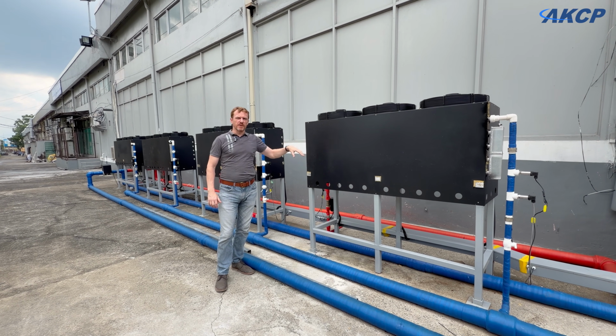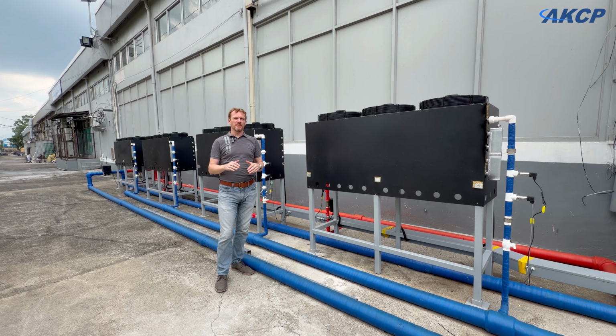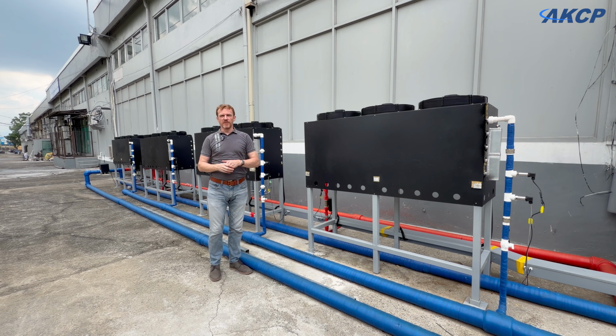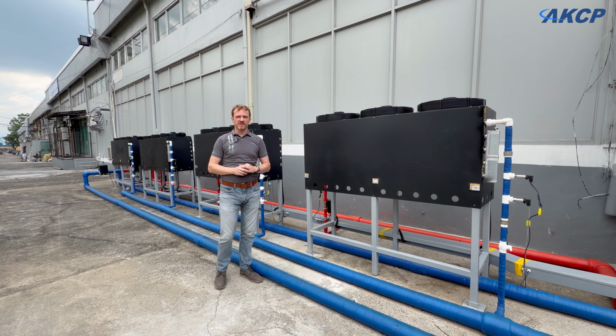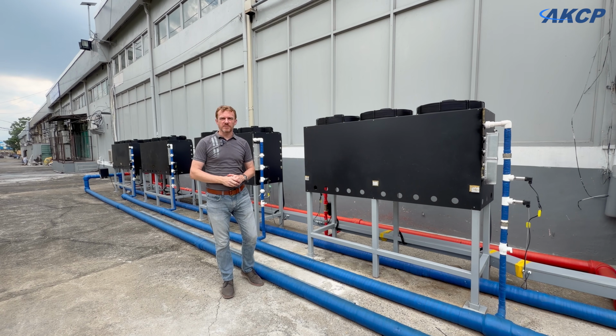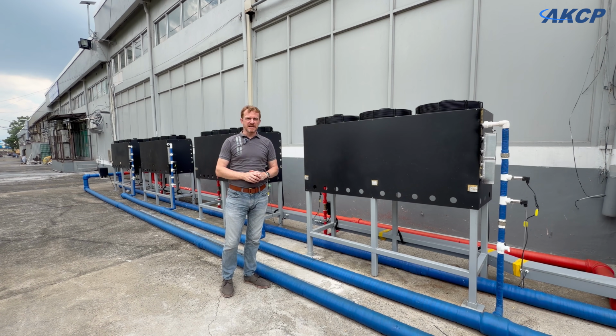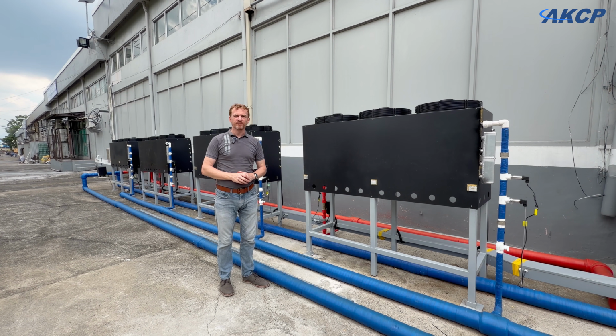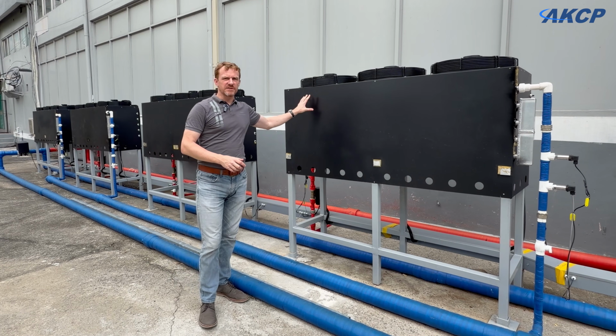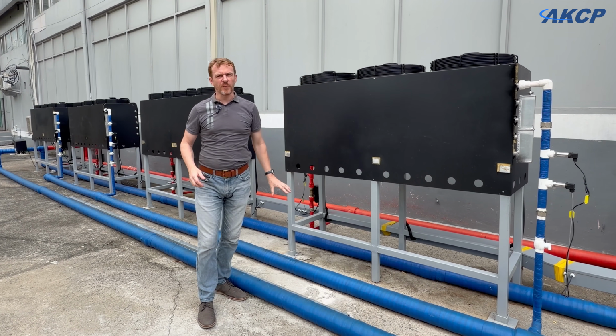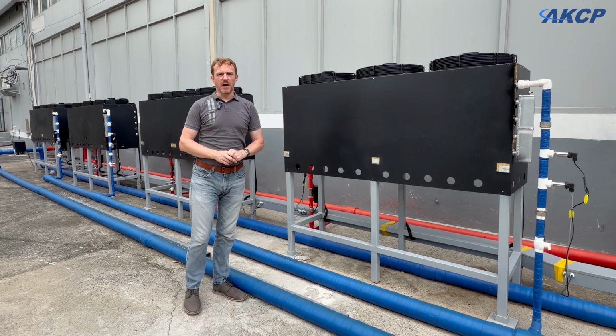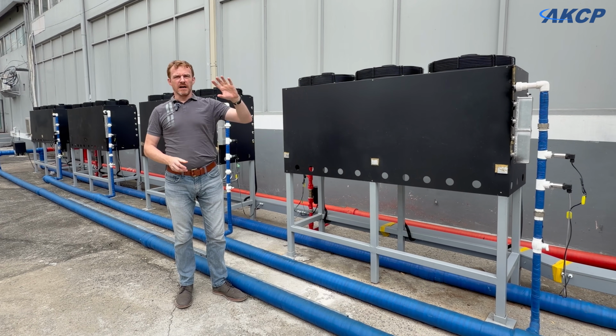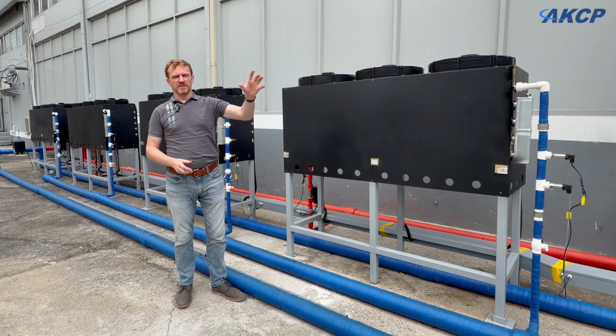We can then drop the temperature of the water to close to ambient air temperature, which here in the Philippines is around 30 degrees most of the time. But it does get down to 24, 22 degrees in the evening at some times of year. So what we can do then is drop the temperature of the water before we send it back to our water tank, which means that we don't have to turn the chiller on as often.